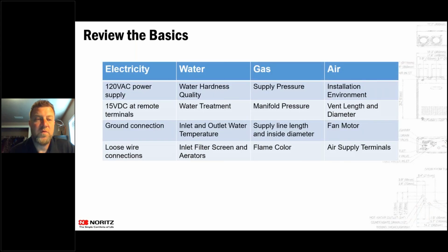So, maintenance with tankless water heaters. We've talked about the flushing and things like that, but some things you'll want to check when you are flushing those units: make sure that the power supply coming in has nothing arcing, that the ground is connected, and there are no loose communication wires. Check the water treatment that they have, or the water quality that's already there. One good thing to do is look at the incoming and outgoing water temperature of the unit and make sure it is actually delivering the temperature it's supposed to.